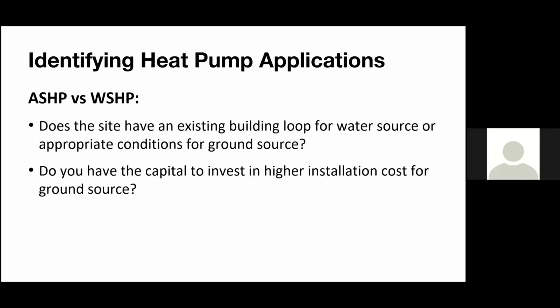Now, your ground source water source heat pumps can generally be lower operating cost than your air source heat pumps. Again, it depends on what you're using for water source heat pumps, like if it's simple on-off compressors or variable speed compressors for the heat pumps, and then also on the hydronic pumping side, if it's variable speed pumping or constant speed pumping. So a couple of things, again, to consider and look at what you're using. And also don't forget that there's also water source VRF that can be used, combining the two technologies there.